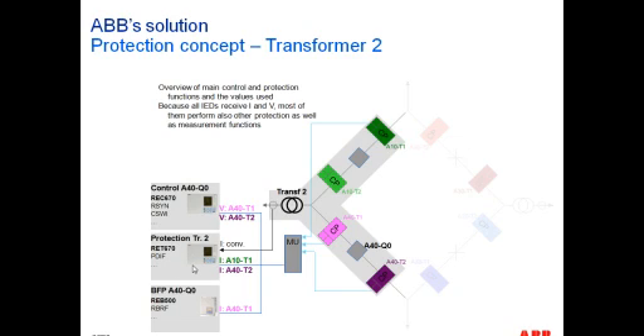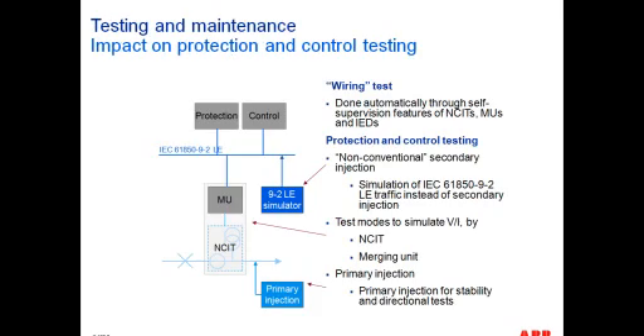So the RET670 actually combined conventional with non-conventional current signals, meaning sample measured values, signals from the high side, and then just conventional hardwired instrument current transformers into the relay for the low side contribution of that transformer.